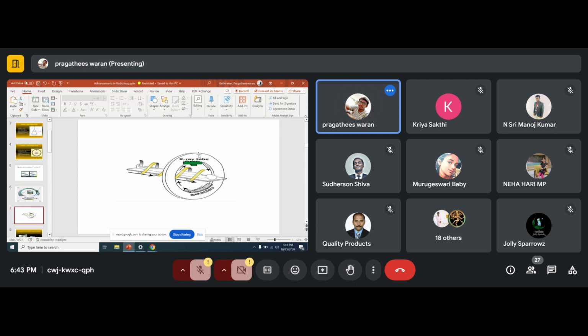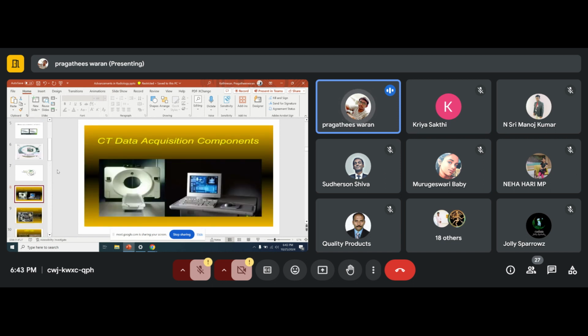So, getting into that, what are the components in the CT? If you say CT, the first thing that comes to mind is the gantry. Inside the gantry, all the electronic components will be there: the X-ray generators, the image acquisition center, the power distribution units, and the patient table. From here this is the examination room, and this is the console room. The console room comprises a monitor, a keyboard, and one control unit for giving information from this monitor to this gantry.